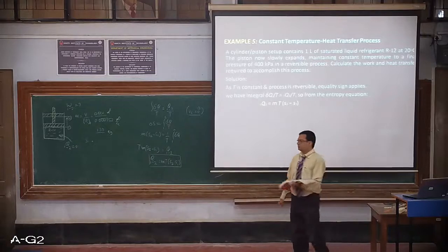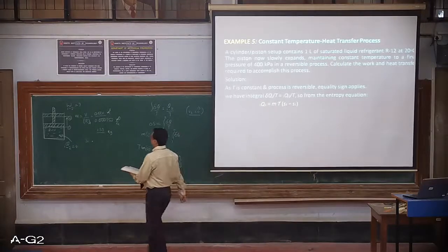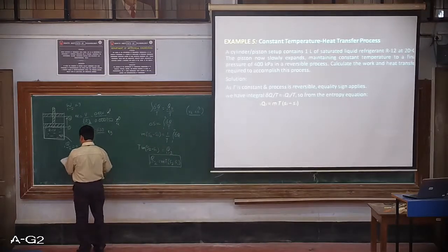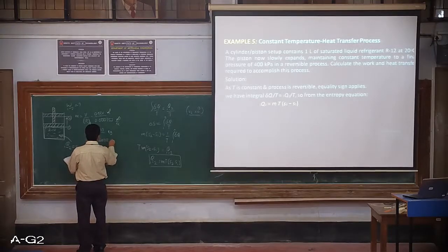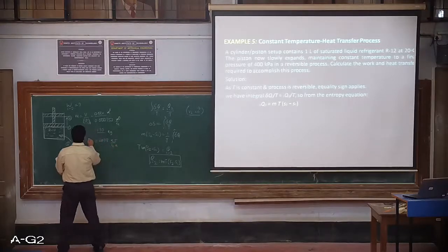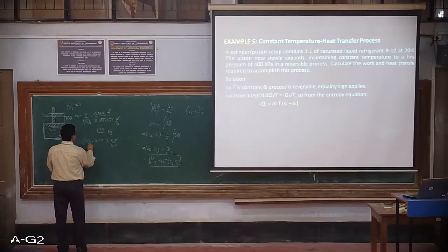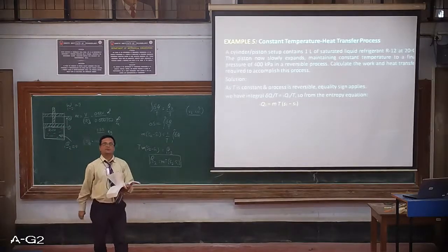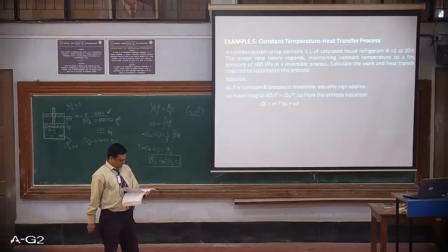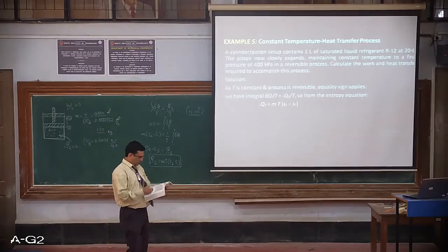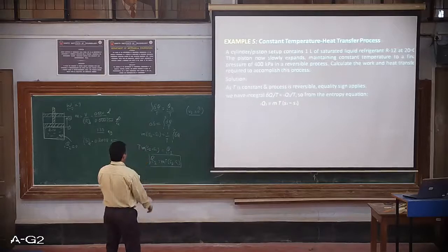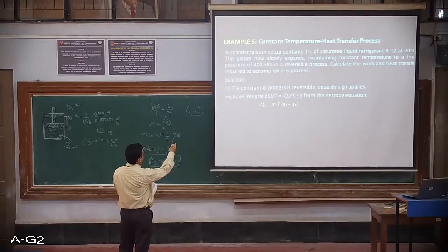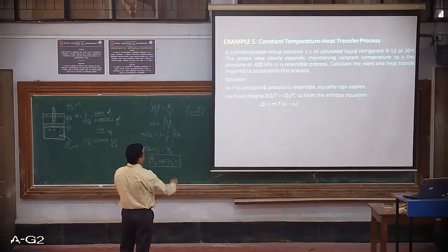I'll give you the values; you can note them down later as 0.2078 kilojoule per kg Kelvin. So again for S1, the property SF is to be looked into, because it is a saturated refrigerant in the saturated liquid form. So we need to look into the SF value in kilojoule per kg Kelvin. Now we have obtained M, the temperature we know, and S1 is known.